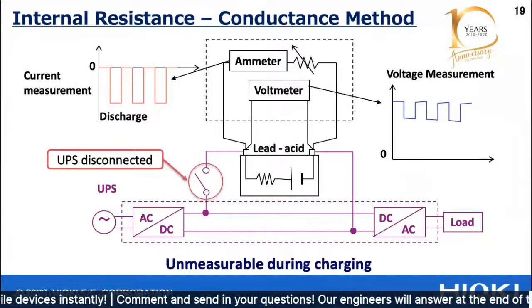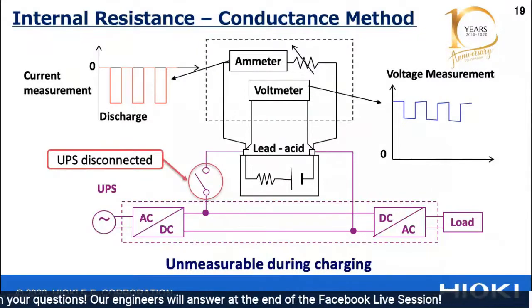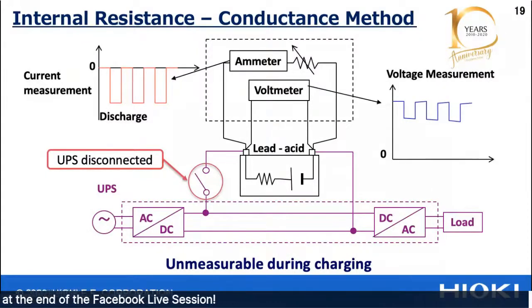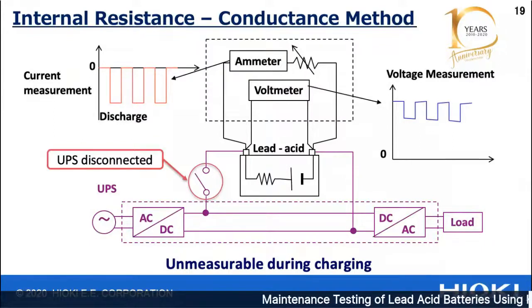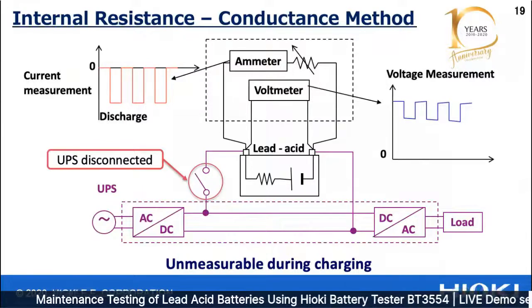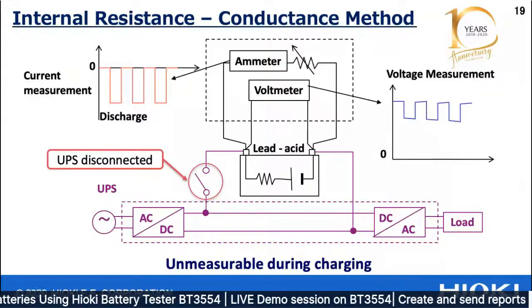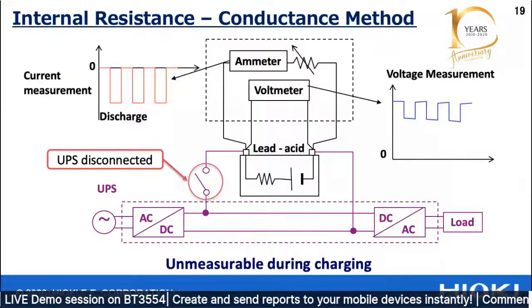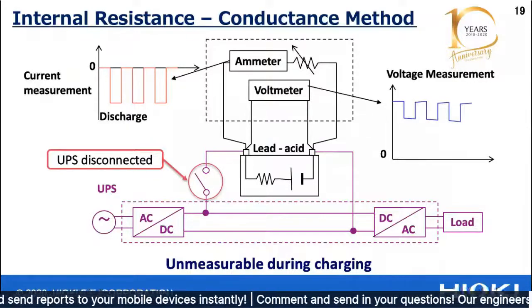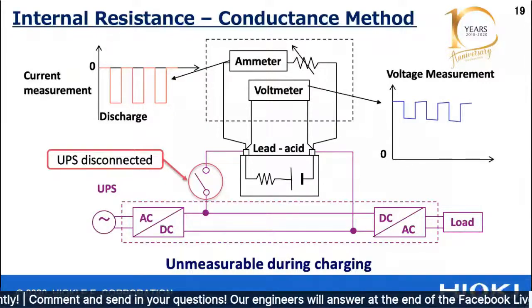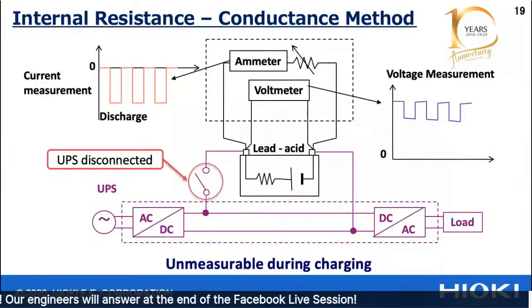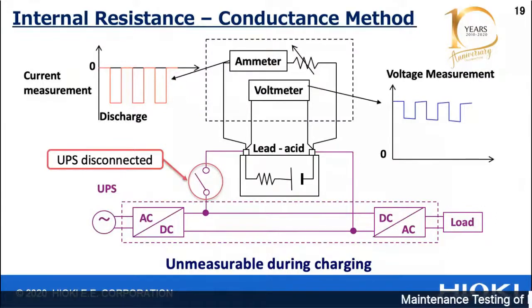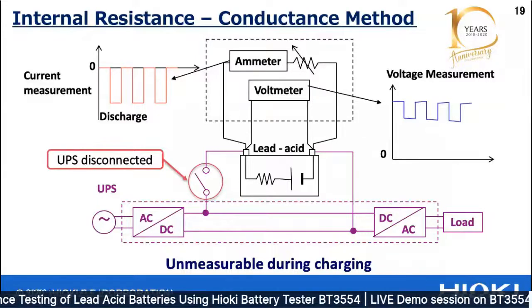When it comes to ACIR, there are two types: the conductance method and the impedance method. Conductance method is basically inversing the resistance - the lower the resistance, the better the conductance, or the ability to allow electricity to flow through the battery. This test is done during the discharge cycle under a controlled discharge current, which is normally very high. The conductance is calculated from the resulting changes in voltage, done with the load disconnected. The drawback of this method is that it is unmeasurable during charging. Other than that, it still uses Ohm's law to calculate the resistance, but inverses it to get the conductance.